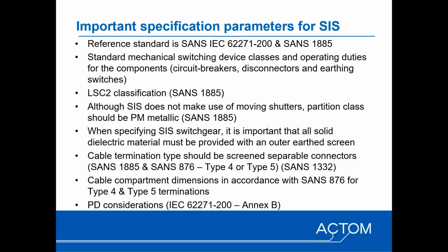So when it comes to single core cables, like for example those used at 33 kV, where we're using 36 kV switchgear, SANS 876 has been amended to accommodate applications where it is known that single core cables will be used, and those dimensions have been reduced.